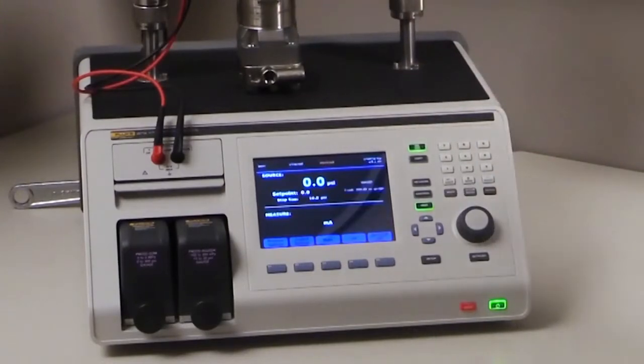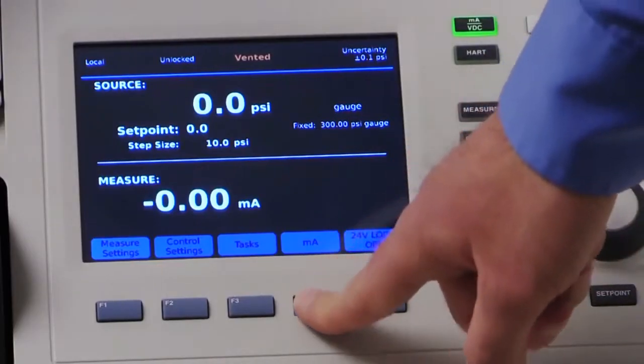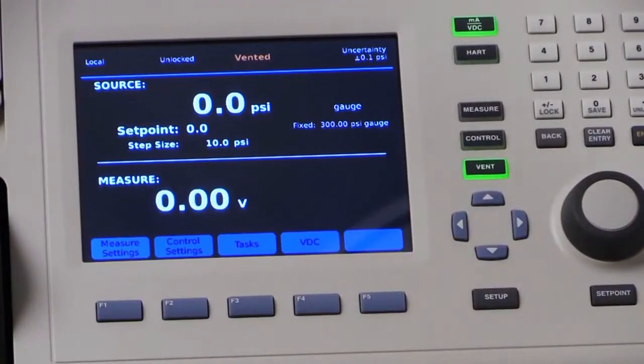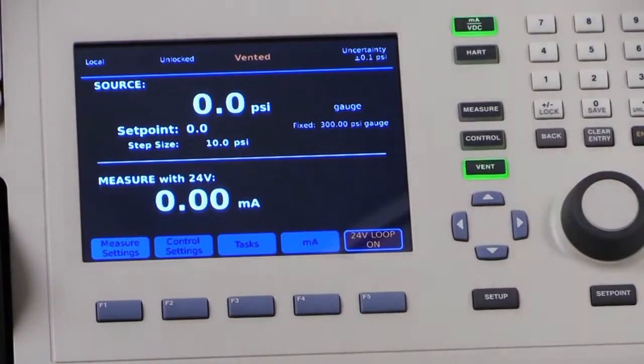To use the EMM, connect the device under test and press the mA VDC button. You can then select between measuring current and voltage, and also toggle the 24-volt loop power on and off.